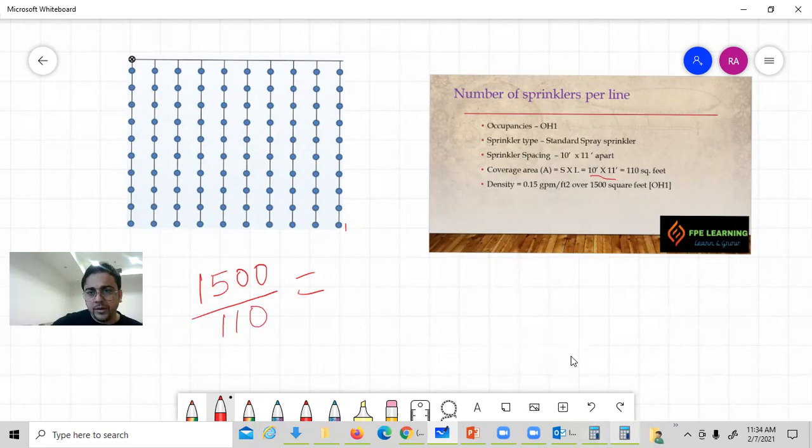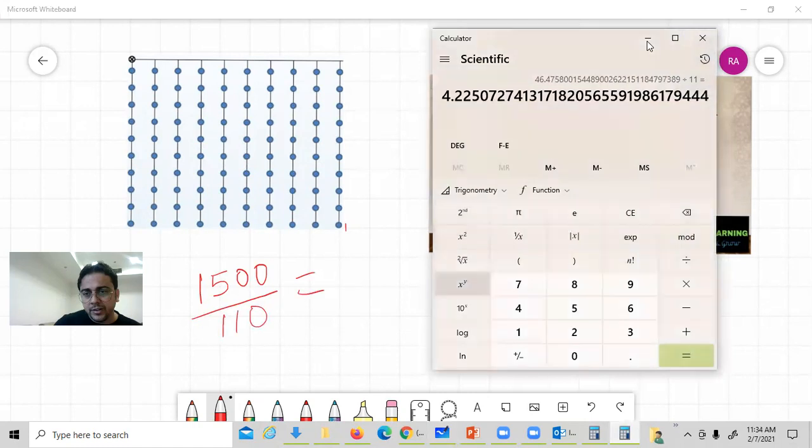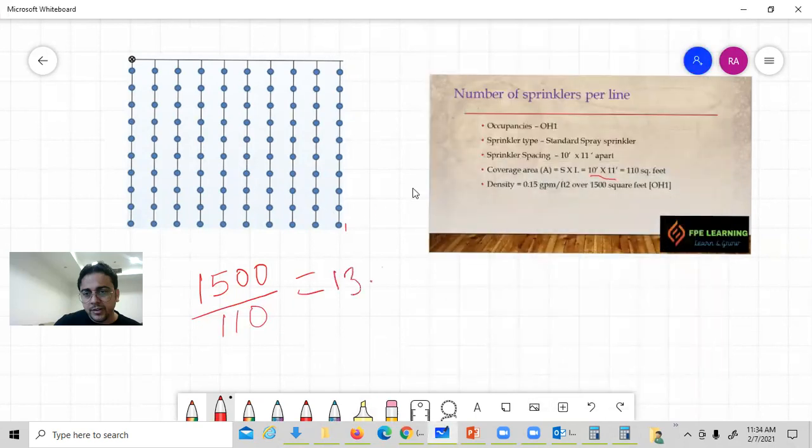I missed one step. If the total design area is 1500 and we have spaced sprinklers by 10 feet by 11 feet, it's 110 square feet. One sprinkler can protect 110 square feet. Total design area divided by 110 equals 1500 over 110, which is 13.6, so let's consider 14. We have to consider 14 sprinklers in our design area.